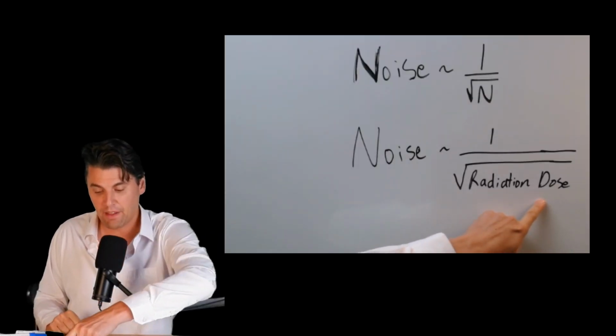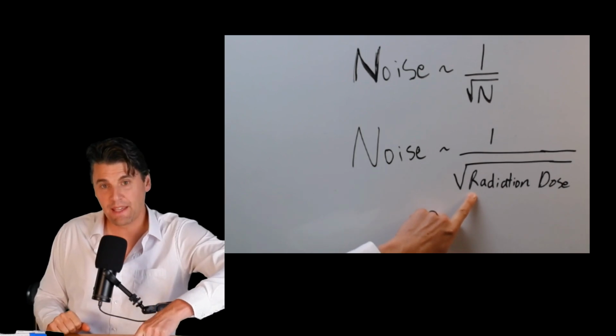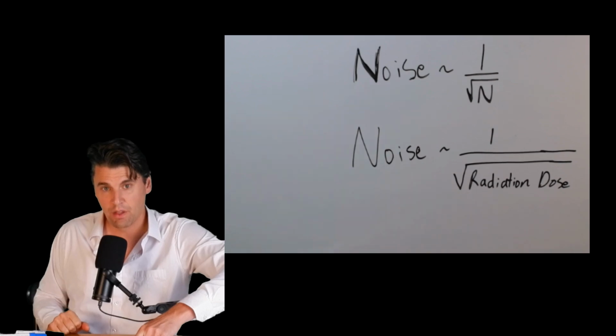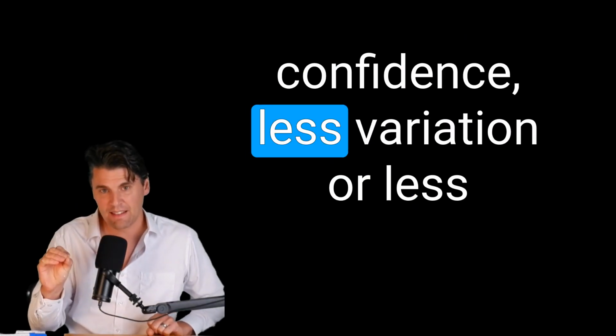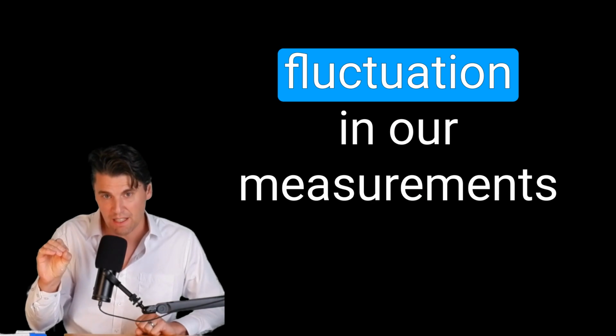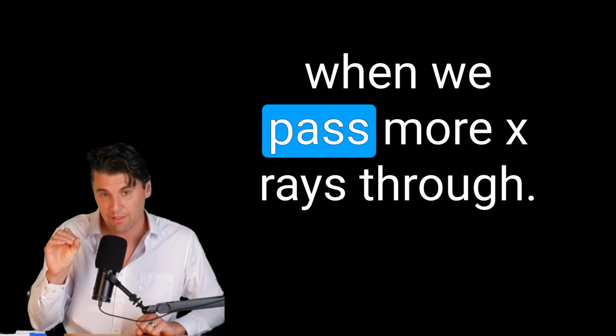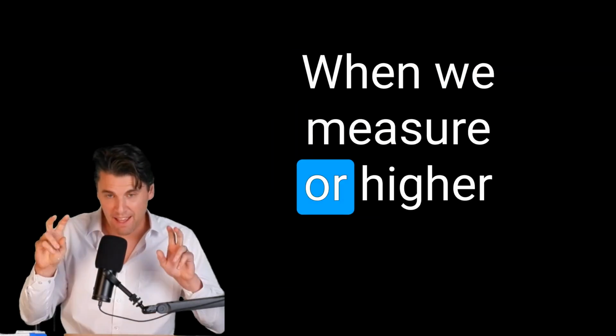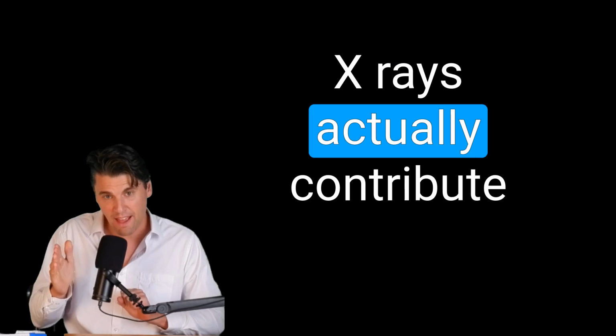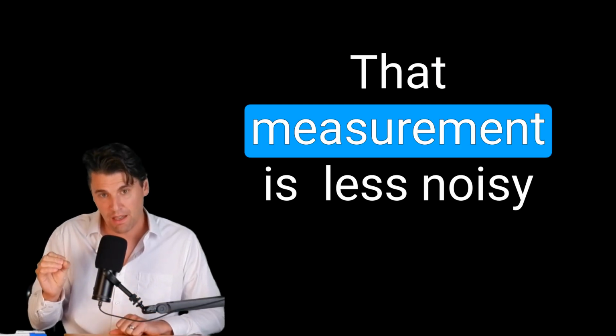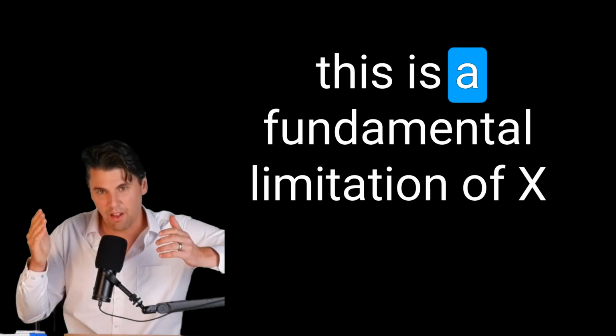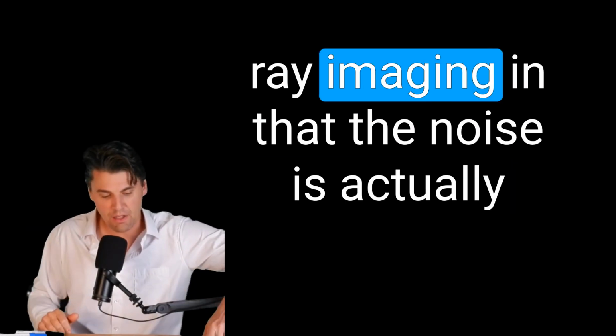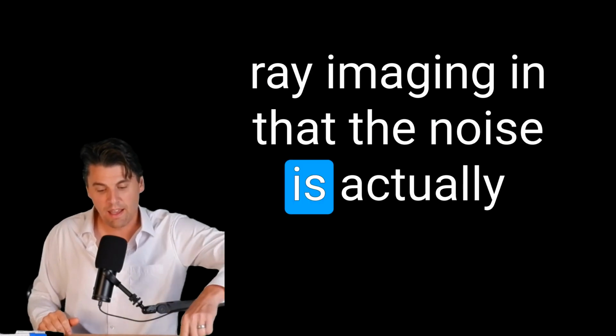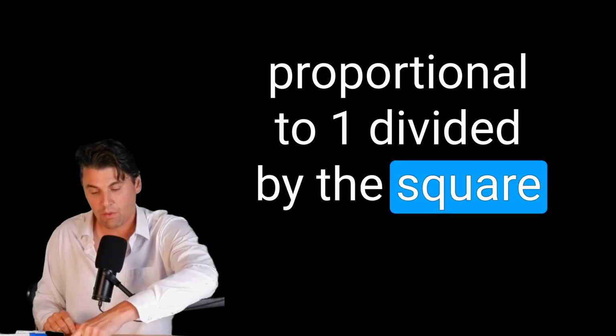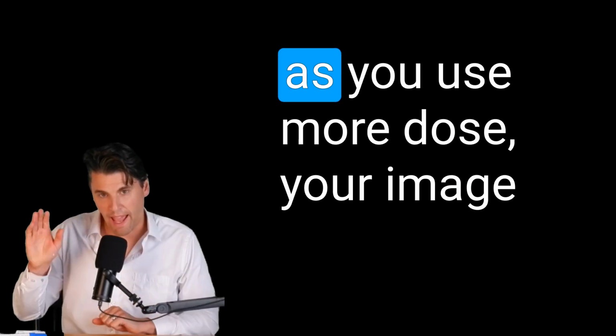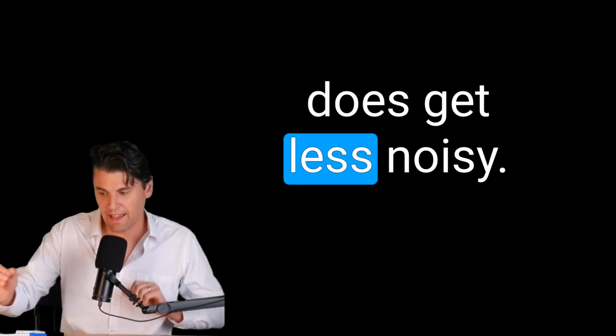Actually, when we end up passing more x-rays through, we end up getting a higher radiation dose. We also end up getting more confidence, less variation or less fluctuation in our measurements when we pass more x-rays through. When a higher number of x-rays contribute to our measurement, that measurement is less noisy. This is a fundamental limitation of x-ray imaging, in that the noise is proportional to 1 divided by the square root of the radiation dose. As you use more dose, your image does get less noisy.